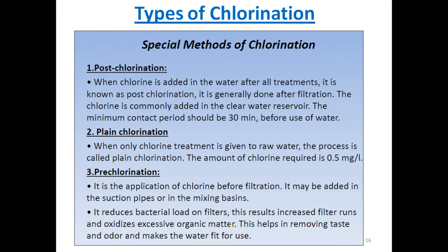The various advantages of pre-chlorination are: it reduces the quantity of coagulants required, it reduces the bacterial load on filters, it helps in maintaining longer filter runs, and it eliminates taste and odor. Also, it controls the algae and planktons in the basins and filters. Now, this was all related to pre-chlorination.